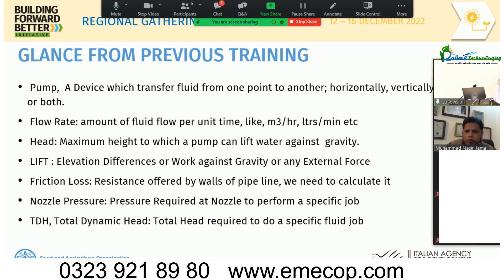Lift is the elevation difference or work done against gravity or any external force. Friction losses are the forces or resistance offered by the valves and pipeline carrying the fluids or water, and we have formulas to calculate these friction losses. Nozzle pressure is the pressure required at the nozzle of a particular equipment like a sprinkler or drip system to perform a specific job.